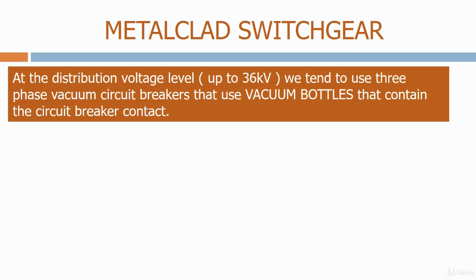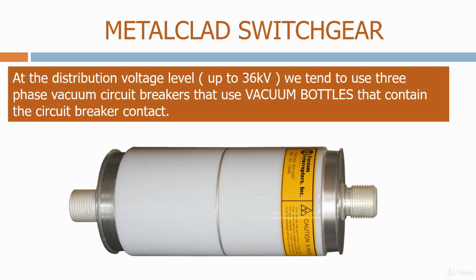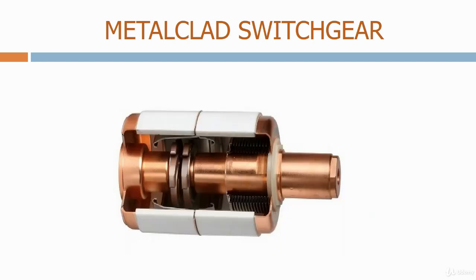At the distribution voltage level, up to 36 kV, we tend to use three-phase vacuum circuit breakers that use vacuum bottles that contain the circuit breaker contact. Here we have a typical vacuum bottle. Let's look inside the bottle. It's got two terminals. One is connected to the fixed contact, and the other is connected to the moving contact. Here we can see how the two contacts come together.